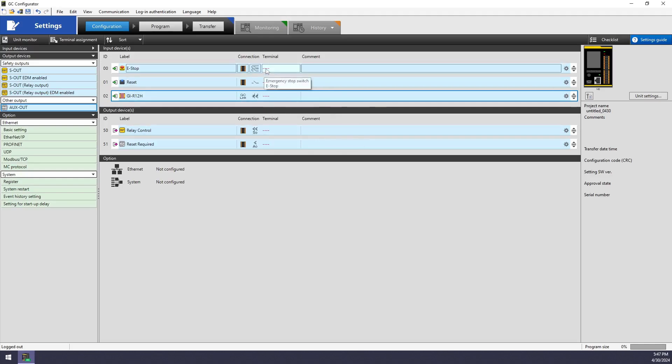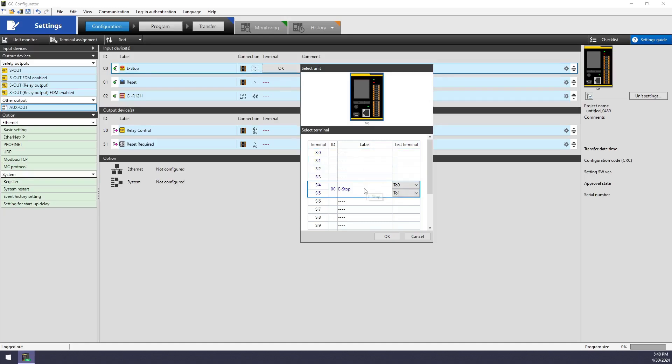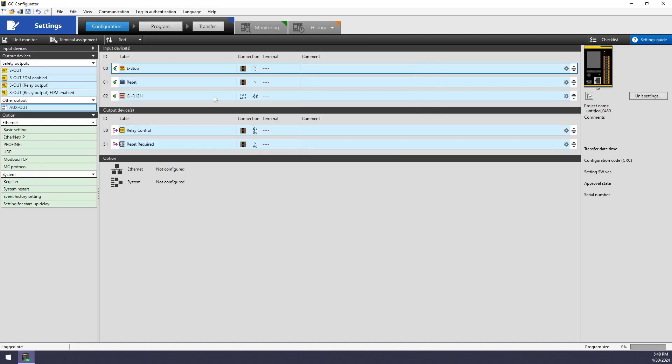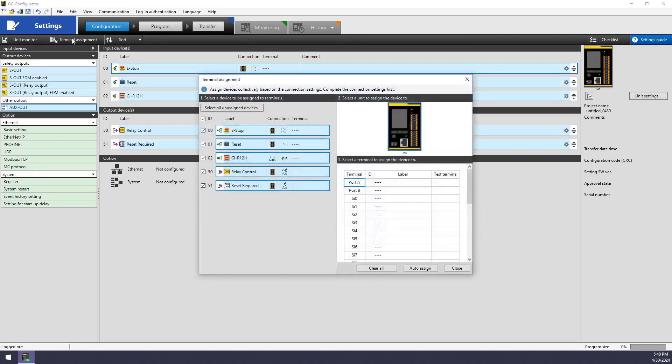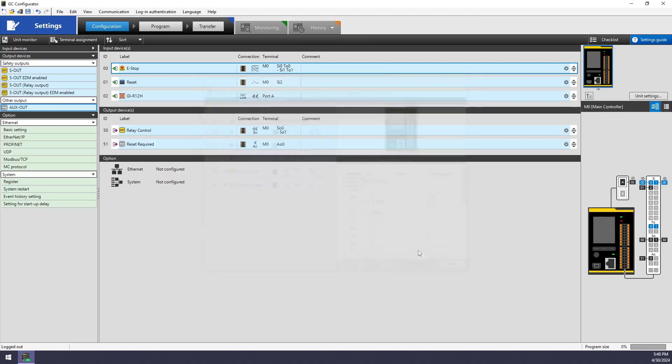To assign the terminals, so you need to tell the GC where that device is going to be connected and the terminal strip, you can go device by device and select the terminals where you'll connect it. But one thing, if you have not done any of the wiring yet, I recommend opening up the terminal assignment, select all unassigned devices, and just automatically assign. For five devices, it doesn't make a huge impact, but if I have 10, 15, 20, that might save me a few minutes of just laboriously clicking.